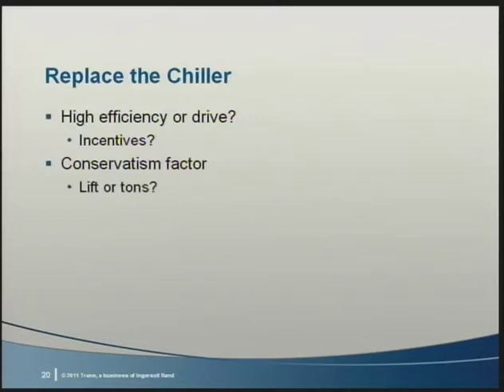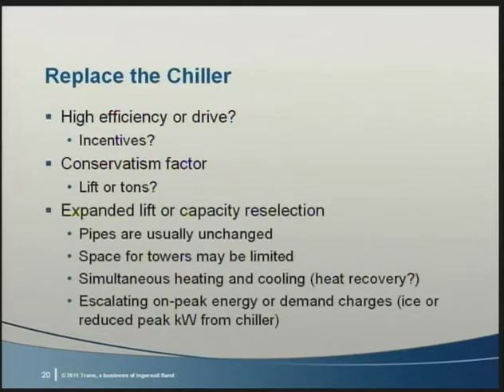In existing buildings, the chilled and condenser water pipes are usually unchanged. If I think I may want to expand the system later, buying an extra chiller might not work because the tons may not fit in the pipe. While Mick is going to go into this topic later, I bring it up now because planning for the future does affect the chiller selection. But in any case, when I replace the chiller, I have to bring it up to today's energy code. Your handouts have the 90.1 2010 requirements for chillers. We just did a program on 90.1, so I'll save some time and skip over those requirements, which are included in the next 4 slides in your handouts.